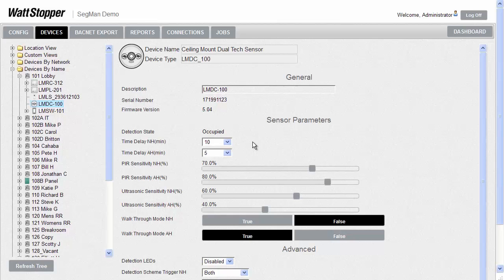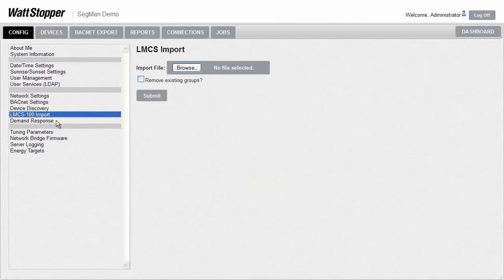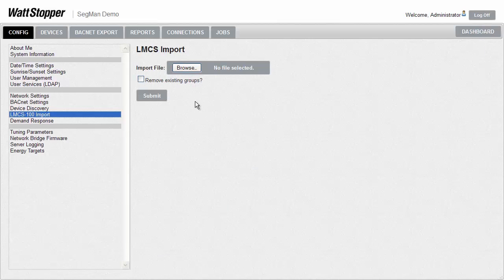Our startup techs use LMCS on the site file to help program the devices on the site. To do that, they first synchronize that file with the individual rooms, so now each device in LMCS also has the actual device's serial numbers. Then they download all the settings. This is important for the next feature. What we've done in the segment is enable it to use the same LMCS file with all those descriptions. By choosing the LMCS100 import option, we can bring that synchronized file in and automatically any descriptions and room names and numbers entered for the DLM items will be applied to the same items inside the segment manager. As I said before, this is possible since both the segment manager and LMCS keep track of every DLM device by its serial number. Ideally, if we've done the programming and have an LMCS file for the site, the tech or the facility manager shouldn't have to type in any of this information themselves.